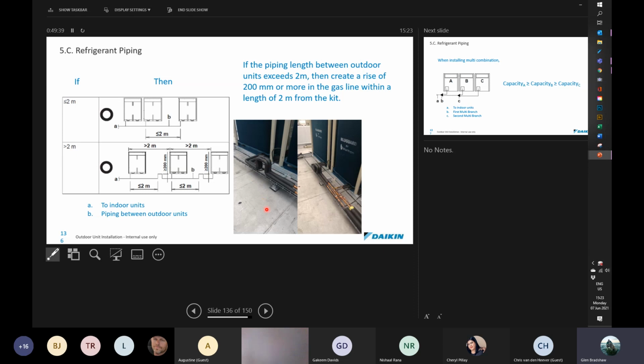Here's an example of a photograph. This is a case where the piping came in from behind into the condensers. It's been done very, very neatly. Because the piping flows around the back, you've got the width of the unit plus the piping over here through the ref net, so you have to put in a gas riser. The gas riser only goes in gas pipes, not in the liquid line. So remember, on a 2-pipe system, it will go in the suction gas pipe, or what we call the suction line. In a heat recovery system, both gas pipes will have one of those installed into it. Never ever put it in the liquid line.